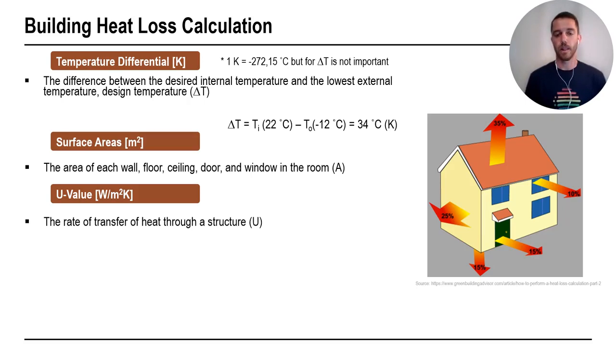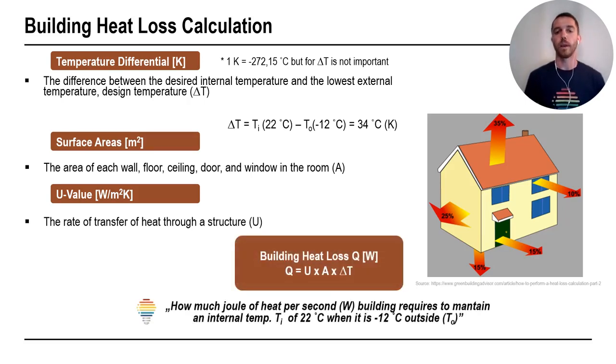And when we put everything together, we have building heat loss, Q in watts. So building heat loss is U multiplied with A multiplied with delta T. Or, in easy and understandable way, this is how much joule of heat per second. So this is what building requires to maintain an internal temperature, for example, 22 degrees when it's minus 12 degrees outside. So we need to know that this is speed. So heat is speed, how much joule of heat per second. And on later slide, we will go more deep inside.